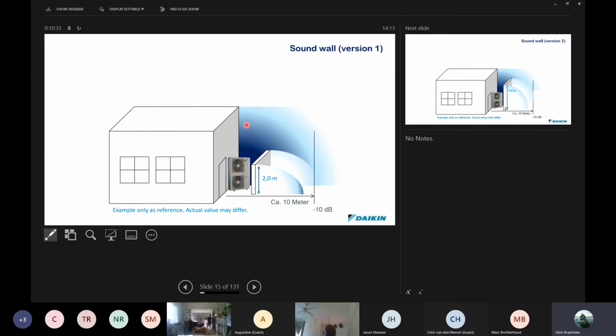Then we spoke about a sound wall, and the considerations for a sound wall are things like height and also what the sound wall is made from. You can get pre-built sound walls, which are louvers with sound deadening insulation, or attenuation, inside them. These do work quite effectively as well. And here we've got a wall of 2 meters, and you can see from the gradient we've killed quite a bit of the sound, but as you go further back you may start to hear a bit of it again, because sound traveling in waves tends to arc away from the sound source. So back here you might start to hear things.